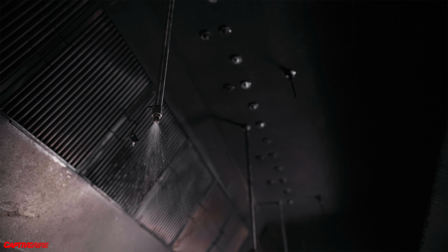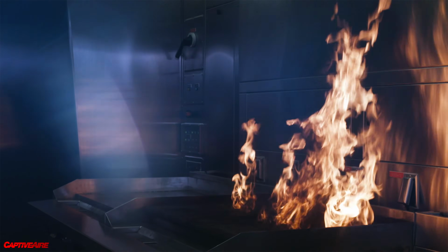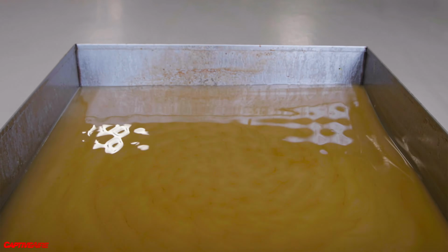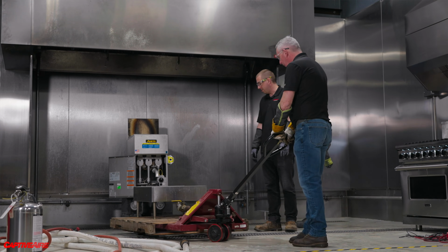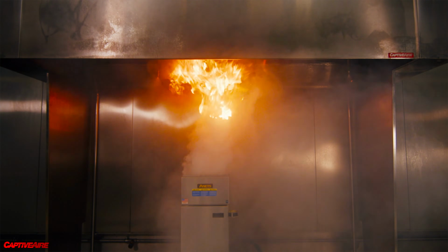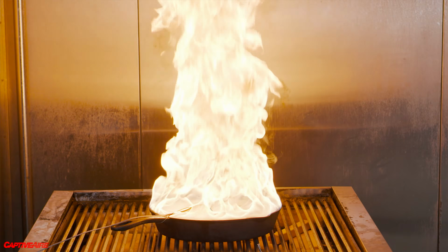The first thing we did for Core, and for Tank as well, was place pans under the hood and test different nozzle patterns, measuring how much agent was getting into those pans. Based on that, we could approximate how much agent we'd be dumping onto fires and into appliances. One fryer may have 5 gallons of oil, and the next fryer may have 80 gallons of oil, so you need a system capable of suppressing all different types of fires, and you have to know how much agent is needed for each appliance type.